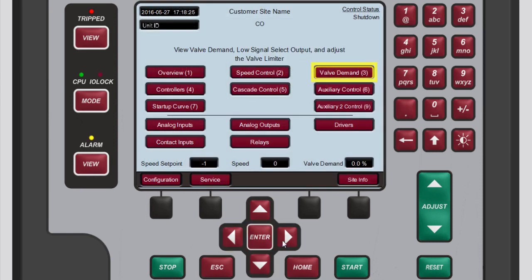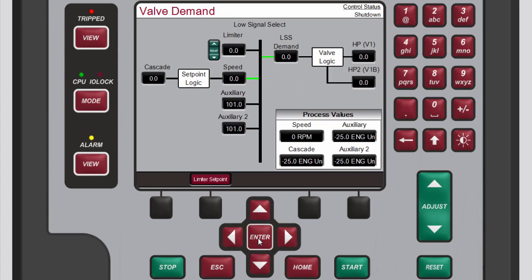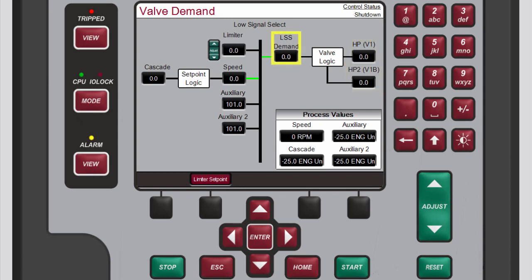The valve demand screen shows all the options that can affect your configured 505's final output demand to the valve. Specifically, it shows us what control or ramp is controlling the valve demand output. The Low Signal Select or LSS bus will output the lowest value seen at its inputs.